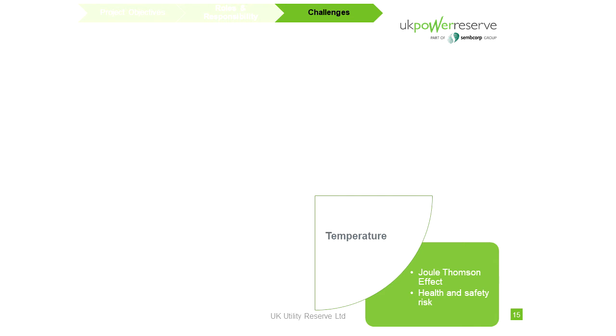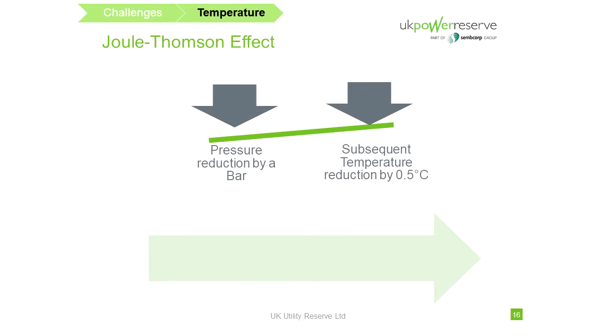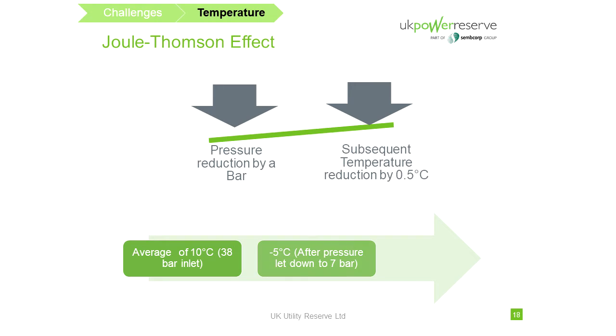However, for most of us that are very much conversant with the Joule-Thomson effect, for every pressure reduction of a bar, there's a subsequent temperature reduction of 0.5 degrees Celsius. So for this particular project, at the inlet pressure of 38 bar, you're having an average temperature of 10 degrees Celsius. And then when it goes down to 7 bar, it drops to minus 5 degrees Celsius. And then subsequently at 250 to 260 millibar, minus 10 degrees Celsius.